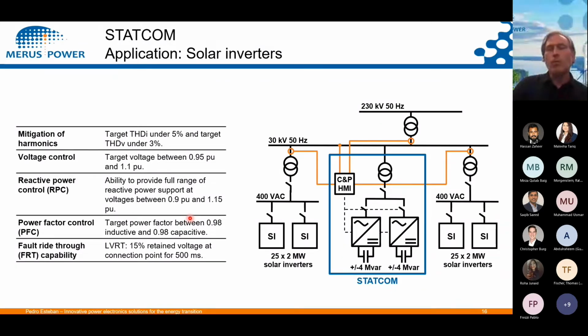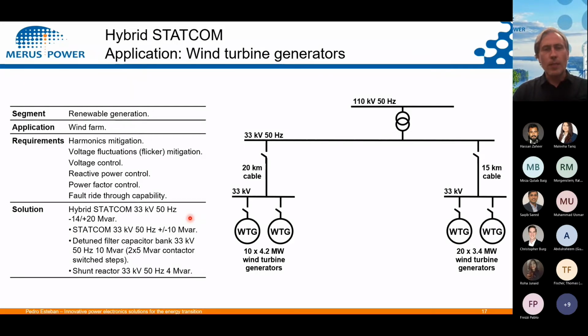The second example will be wind farms. In wind farms we actually have two types of equipment that cause problems. One of them is the wind turbine generators. But also an important issue in wind farms is cables, because cables are capacitive and there are huge distances of cables in wind farms, so they also create certain problems. From the wind turbine generators you can see the harmonics that are created, there can be issues with flicker, plus we need to be able to control certain parameters of the operation of the whole wind farm. So in this case, a hybrid STATCOM could be a good solution.